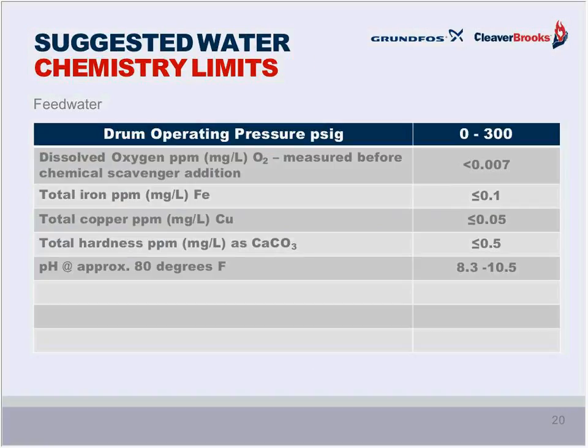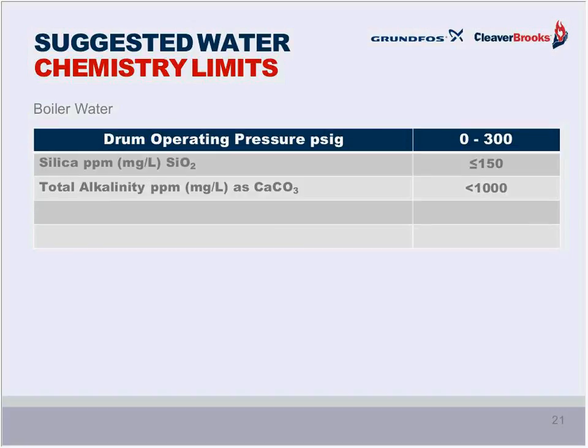For instance, as far as limits of oxygen are concerned, many consultants want to limit the oxygen to 0.007 milligrams per liter in the feed water, while also limiting other contaminants. As far as silica and alkalinity are concerned, here are suggested limits for those when operating at pressures between 0 and 300 psig. 300, by the way, is equivalent to 422 degrees Fahrenheit.